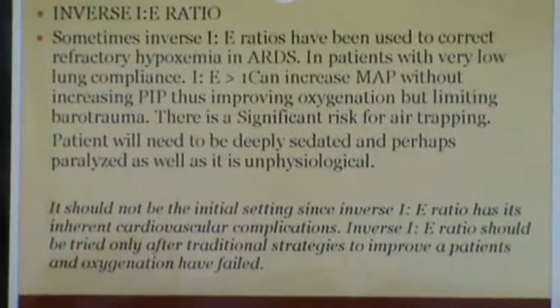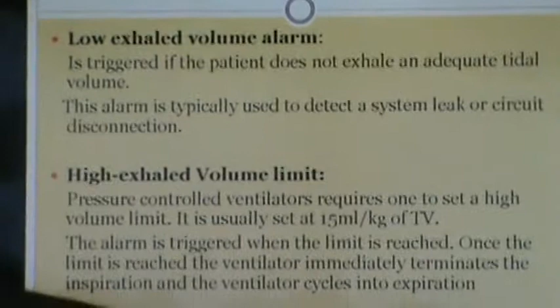Generally we set a few alarms after setting the basic parameters. Low exhaled volume alarm: if triggered, the patient is not exhaling adequately, and it will detect circuit leak and disconnection. High exhaled volume limit: pressure control will require one to set a higher limit, set at 15 ml per kg, and the alarm is triggered when the limit is reached. Once the limit is reached, the ventilator will terminate the inspiration and expiration will begin. That will thereby prevent volutrauma and barotrauma.